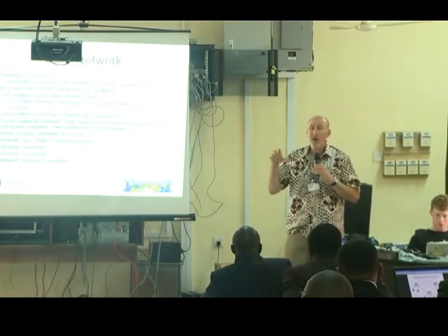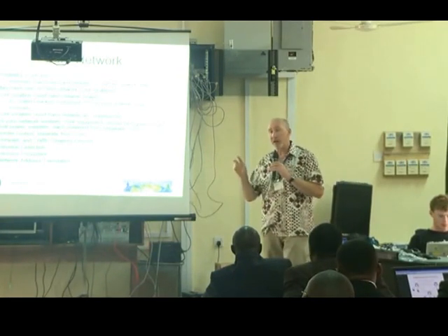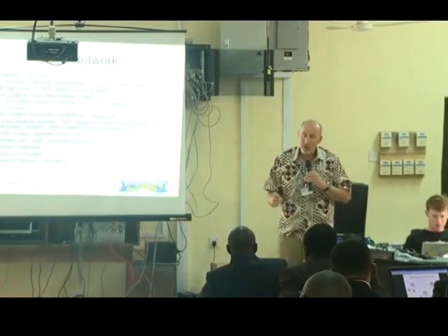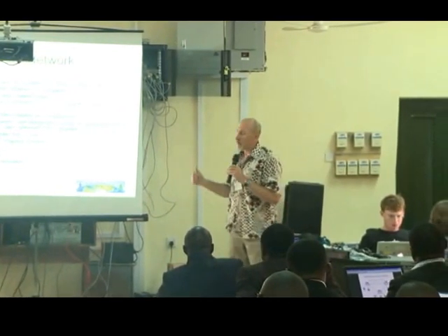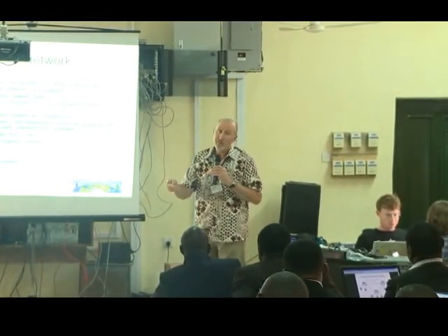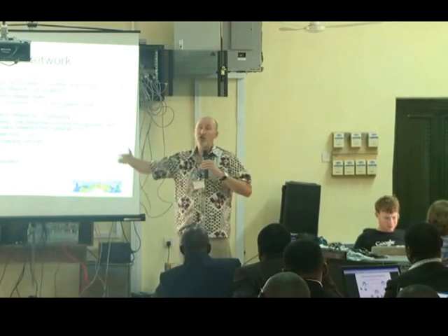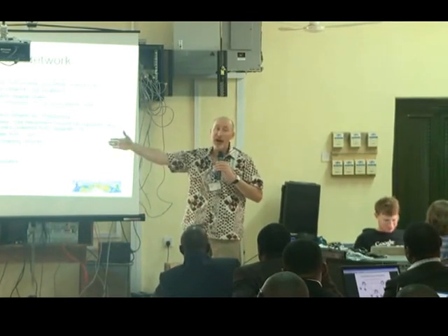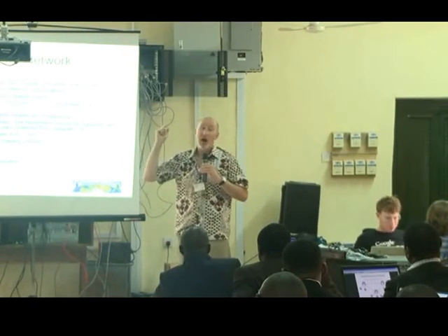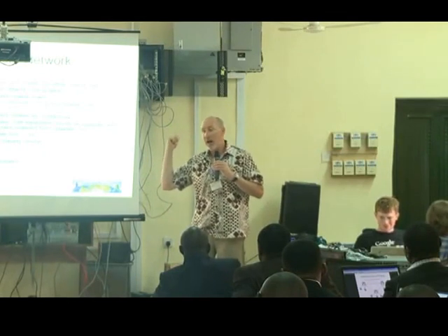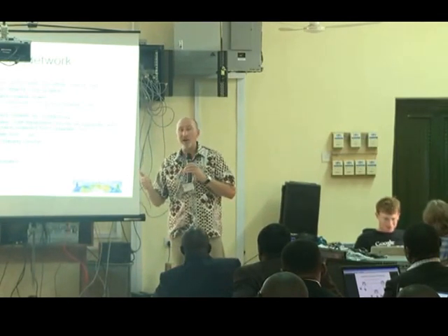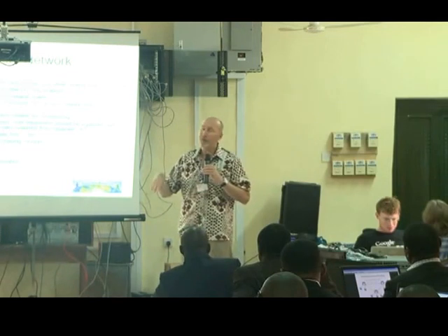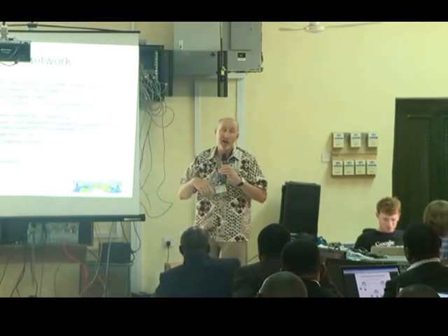So redundancy and reliability are key in the core. In my cores, I have dual UPSs, two big UPSs. I have two power feeds from two different directions to my buildings. I have redundant air handlers, so if one air conditioning unit fails, no big deal. There's another one there that can take up for them.